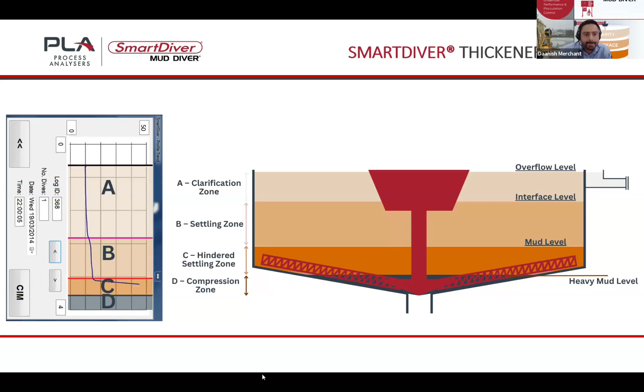This can also be represented in the form of a trend profile, since it takes multiple dives during the day, and it can be mapped into a trend profile. So we can monitor how flocculation is affecting the settling rate. You can see the settling zone between the pink dots, representing the interface, and the green line, which is the mud level. There is a steady gap between these two, which denotes that the flocculants are at their optimum capacity.